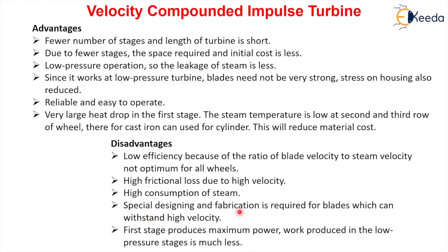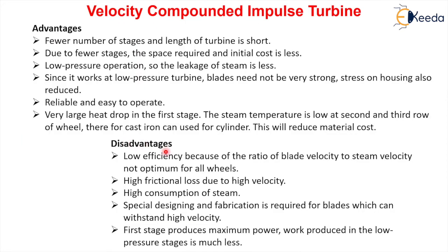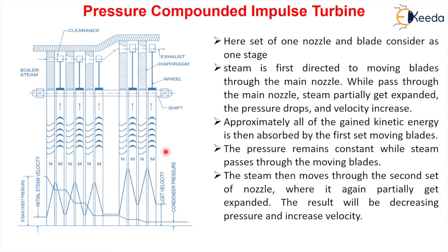Special design and fabrication is required for blades that can withstand high velocity. The first stage produces maximum power, but work produced in the low-pressure stages is much less, so to get constant power output (e.g., 50 MW), steam consumption by this turbine will be very high. These are the disadvantages of the velocity compounded impulse turbine.